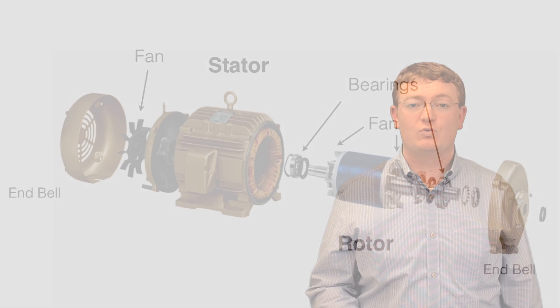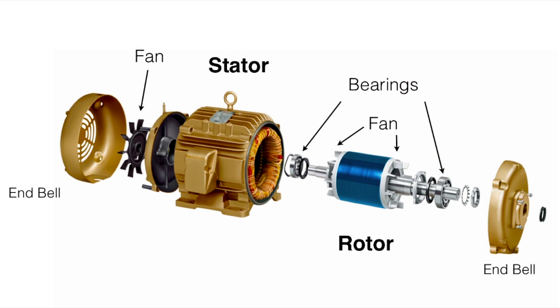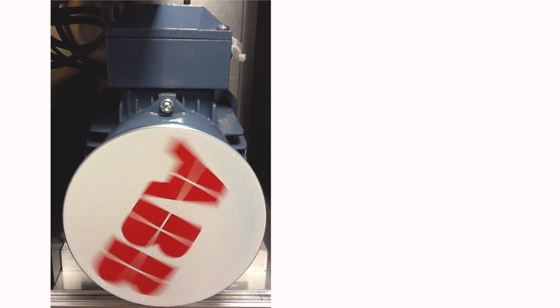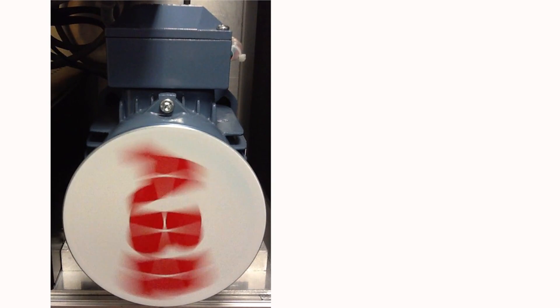Even further, flux optimization allows motors to be run at lower and lower frequencies. Generally, people set the lower limits of a drive to around 20Hz — in some cases even more. The reason for this was that as motors slow down, their ability to deliver air across the windings via the internal fan blades is reduced. Therefore, at those lower frequencies, motors would overheat. But because flux optimization takes the heat out of the windings of the motor, we can operate at those lower frequencies, so long as we don't stall the motor. We have consistently seen, when flux optimization is used, that motors can be driven down to 3Hz, saving even more money.